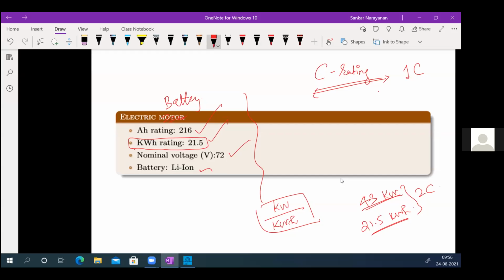Okay, the battery voltages are really fixed. The voltage changes in the batteries are very less. If you take a 48 volt battery, it can go down to 46 worst case, and up to 52 in full charge, open circuit voltage, full charge being 50.